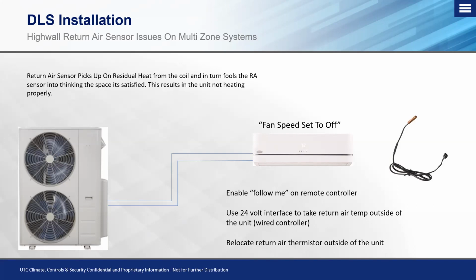Okay, so those are going to be the two options. Again, the first option is typically going to be relocating the return air thermistor to the right side of the unit outside of the cabinet so it reads a true return air temperature, and also programming our fan speeds to shut off after set point. If you have a 24-volt interface, the only thing you need to do is just shut the fan speed off after set point as the interface reads temperature exterior to the unit as a default.